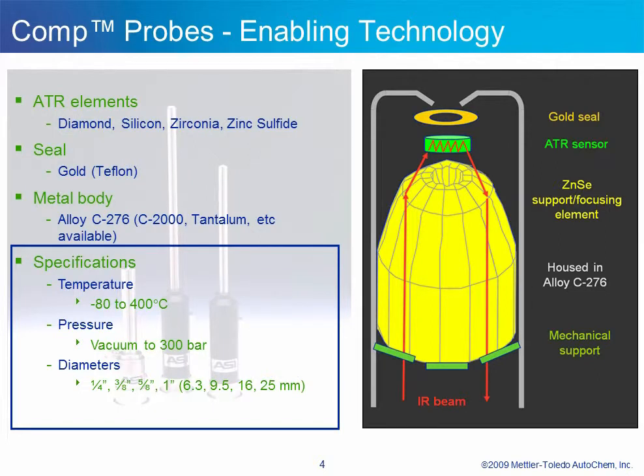In addition to the gold seal, a Teflon seal is also available. Many different types of probe housing materials can be used as alternatives to alloy C276, including tantalum, titanium, or other alloys. The temperature and pressure specifications for the COMP probes are dependent on the specific probe type, but the full temperature range is minus 80 to 400 degrees C, and the pressure range is vacuum to 300 bar. The COMP probe design is available in four diameters: 6.3 mm, 9.5 mm, 16 mm, and 25 mm, all coming in various lengths.